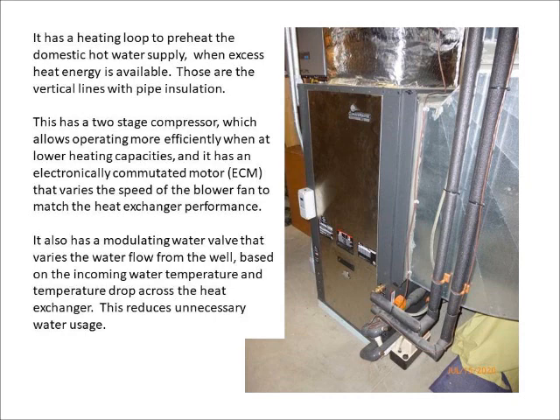This is a two-stage compressor which allows operating more efficiently at lower heating capacities, and it has an electronically commutated motor that varies the speed of the blower fan to match the heat exchanger performance. It also has a modulating water valve that varies the water flow from the well based on the incoming water temperature and temperature drop across the heat exchanger. This reduces unnecessary water usage.